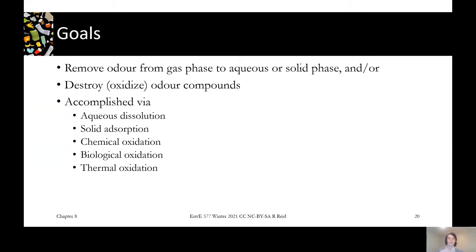Our main goals in our odour treatment step are to remove the odour from the gas phase and into an aqueous or a solid phase, so leaving our clean air to go off into the environment again. And we want to destroy, usually oxidize, the odour compounds. Some technologies will just capture it and then dispose of the sorbent, but it's always better if you can treat that compound as well so it's not going to produce odour problems down the line. And there's a number of technologies that do this, capturing and destroying that odour.